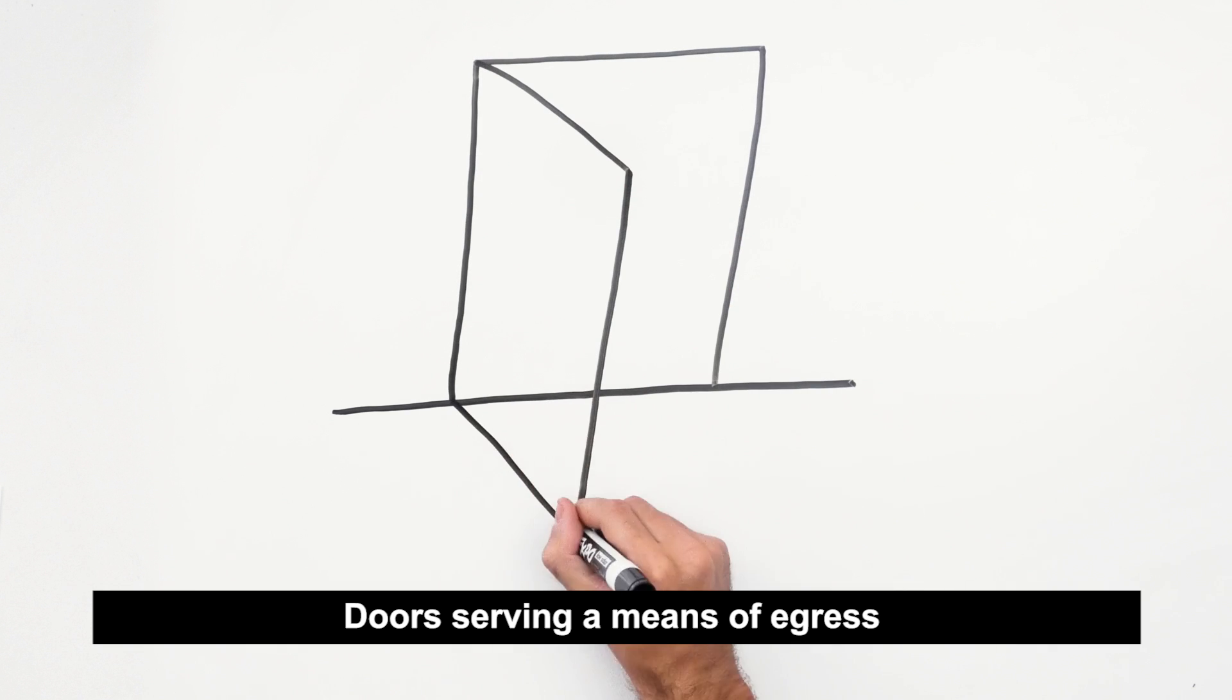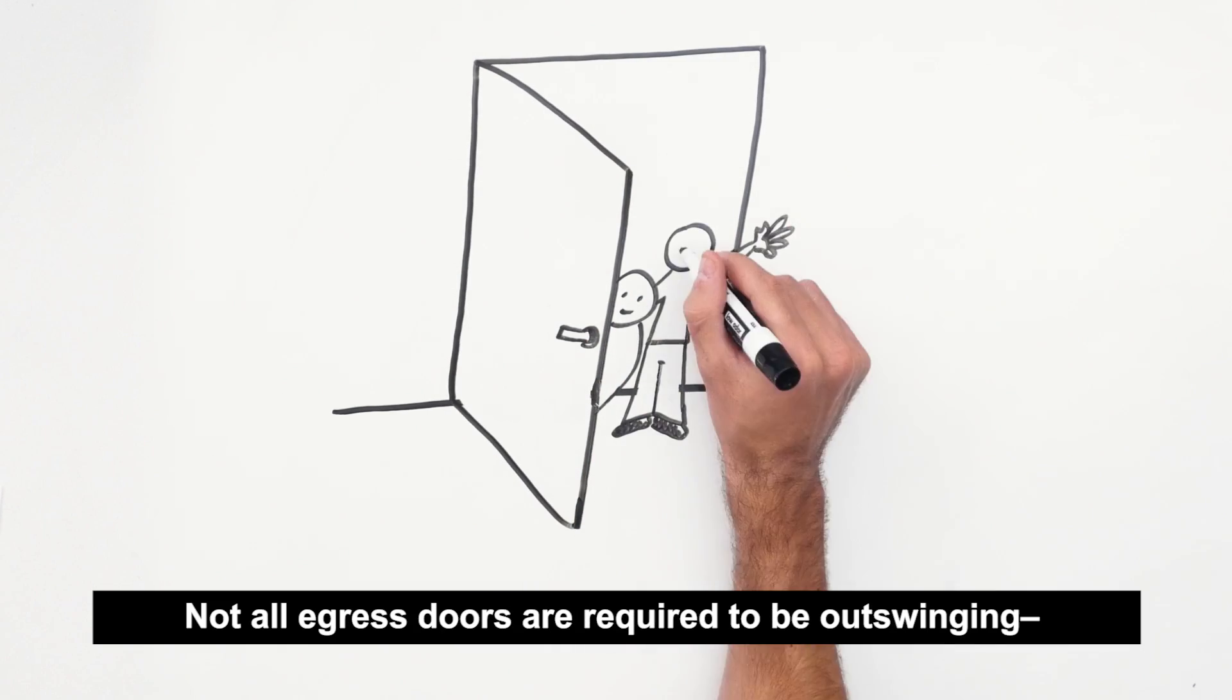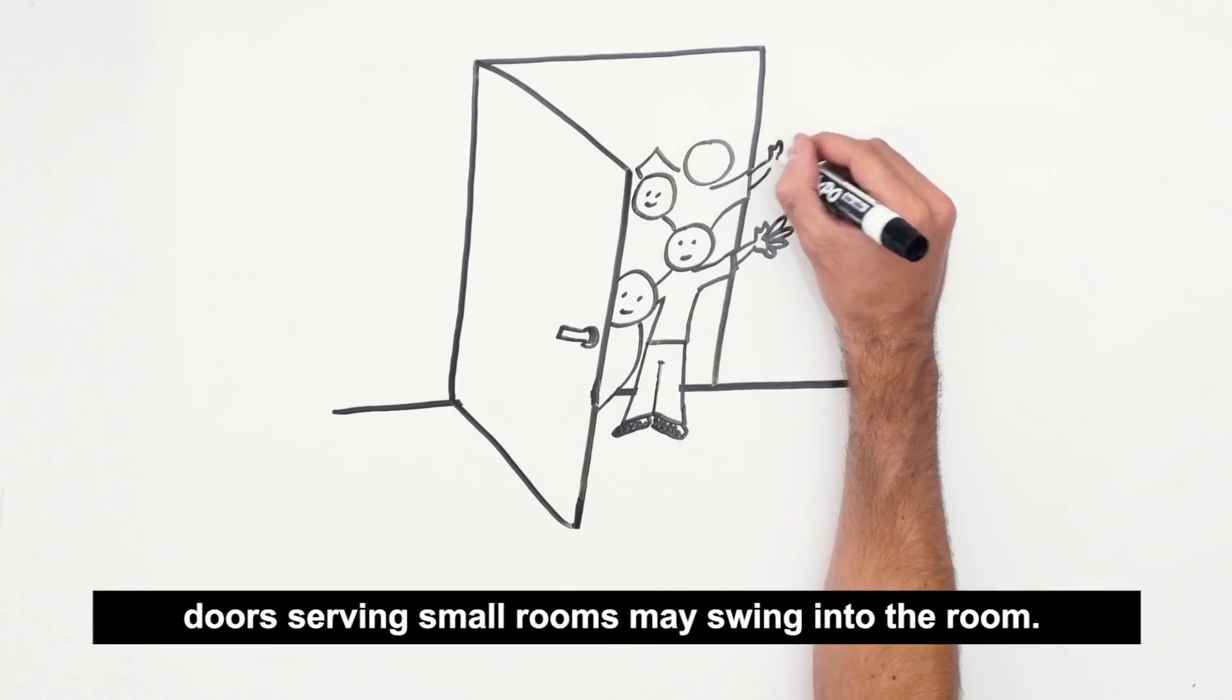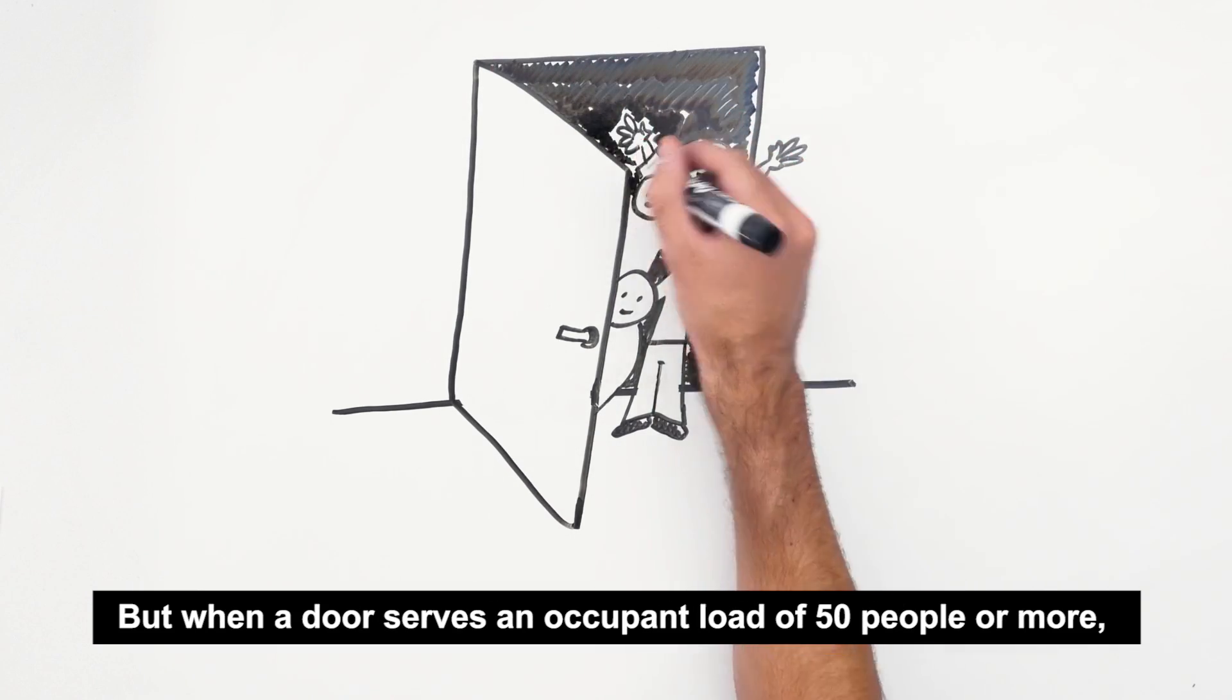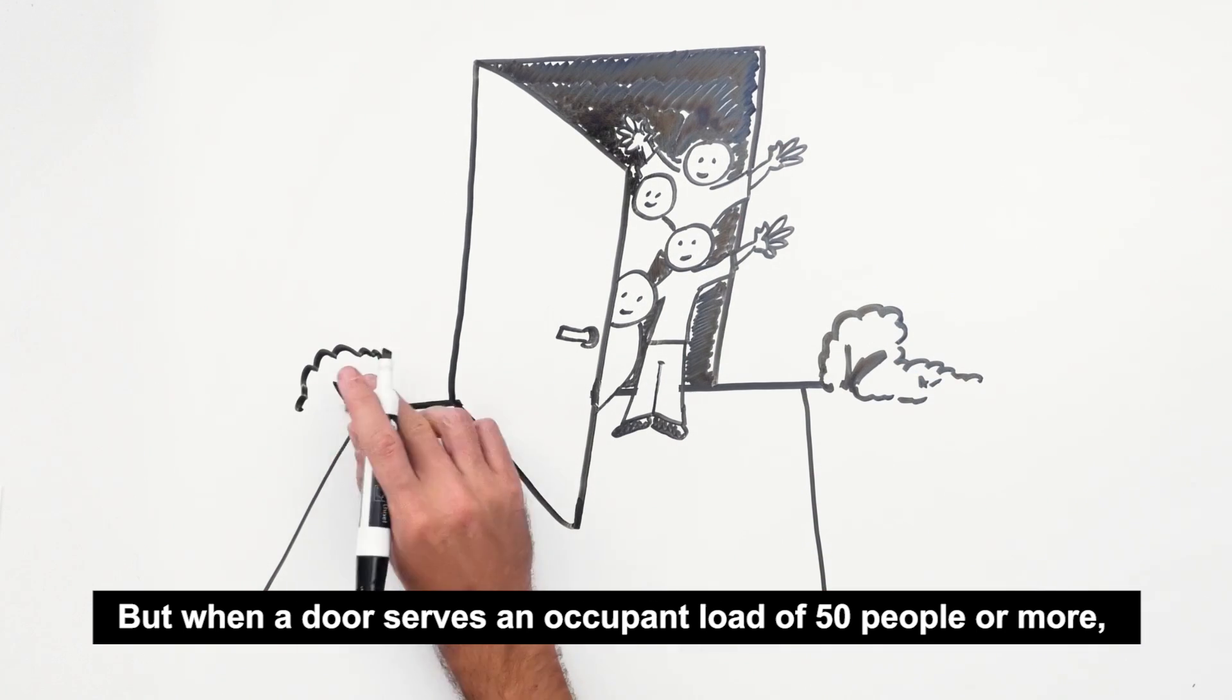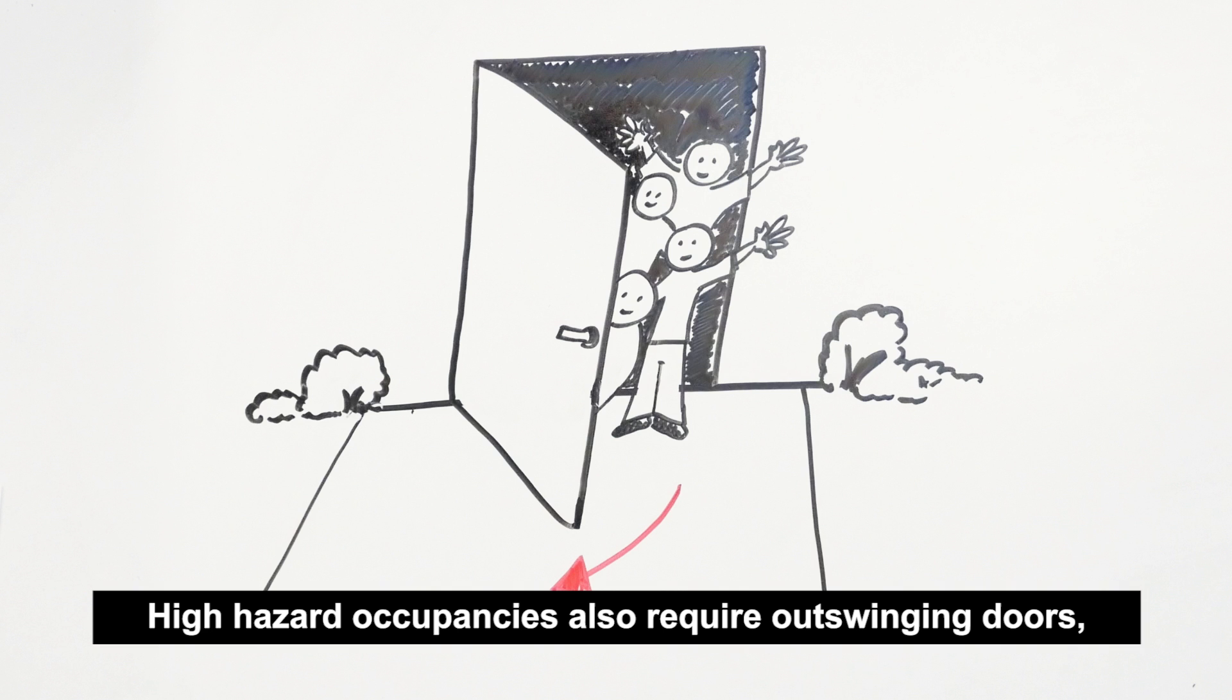Doors serving a means of egress are usually required to be swinging doors. Not all egress doors are required to be out swinging. Doors serving small rooms may swing into the room, but when a door serves an occupant load of 50 people or more, it must swing in the direction of egress. High hazard occupancies also require out swinging doors, and NFPA 101 requires doors used in an exit enclosure to be out swinging.